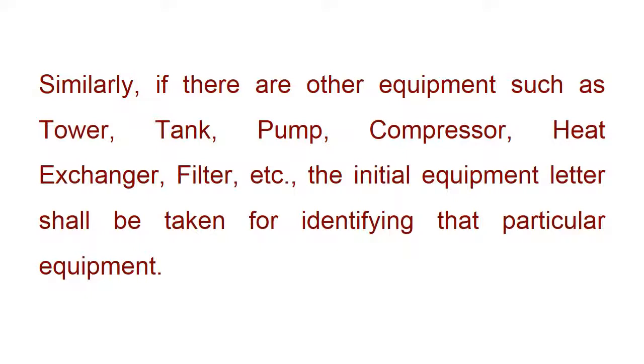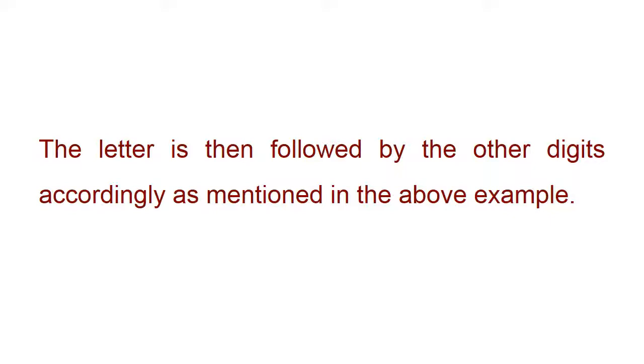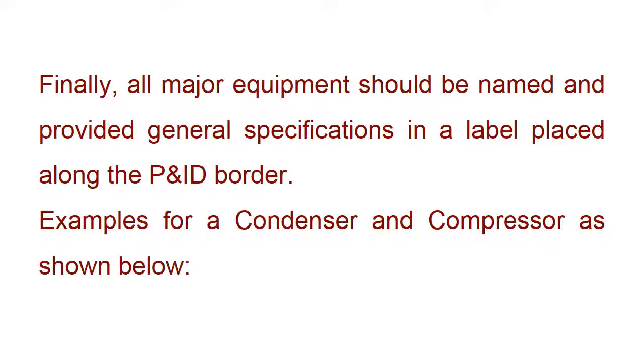Similarly, if there are other equipment such as tower, tank, pump, compressor, heat exchanger, filter, etc., the initial equipment letter shall be taken for identifying that particular equipment. The letter is then followed by the other digits accordingly as mentioned in the above example. Therefore, equipment identification tags could be assigned by listing the equipment on the particular unit under consideration. Finally, all major equipment should be named and provided general specifications in a label placed along the P&ID border, as shown in examples for a condenser and compressor.